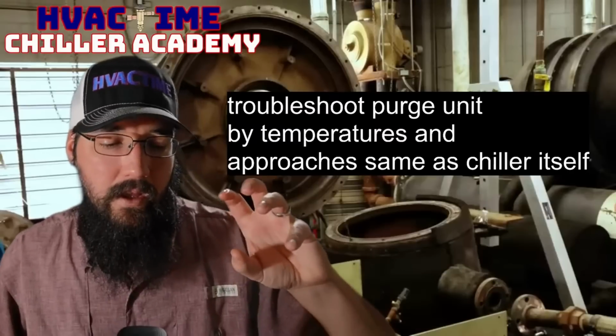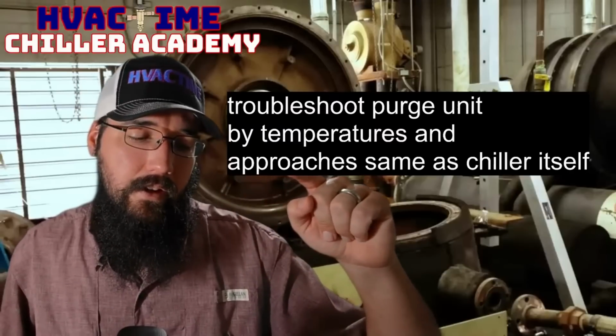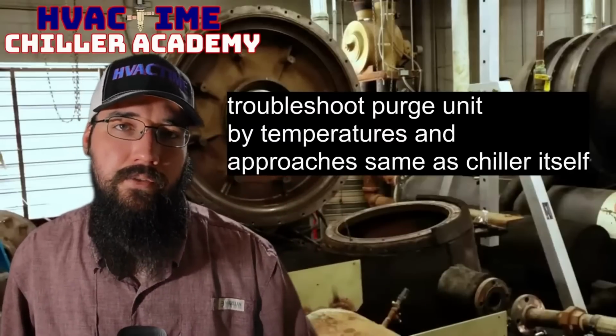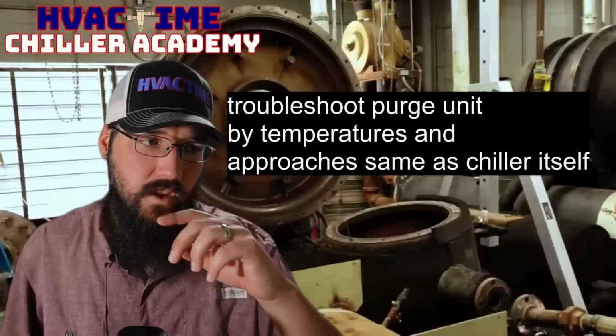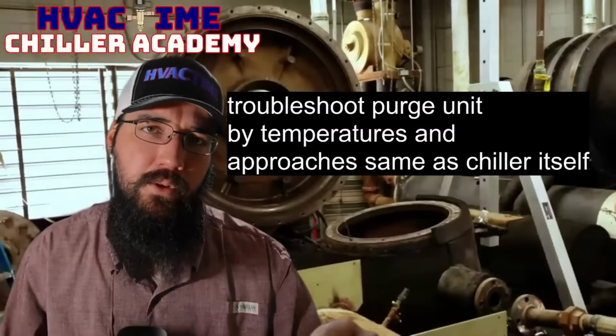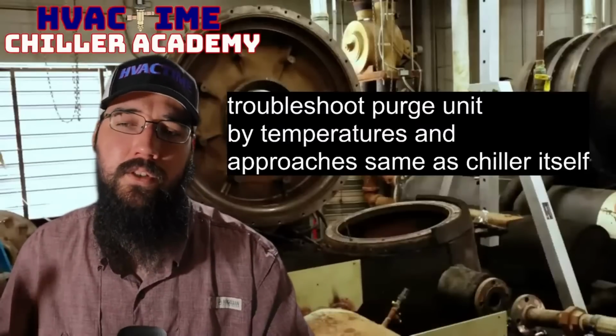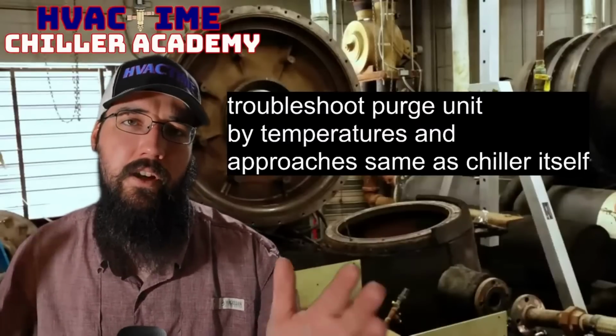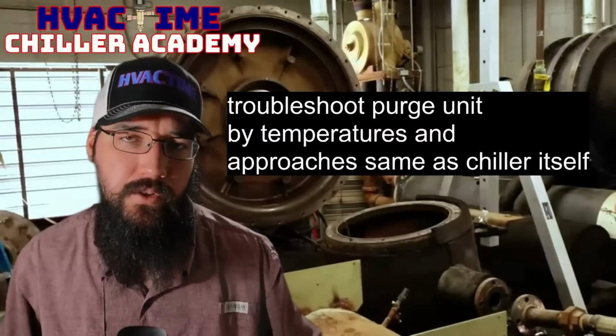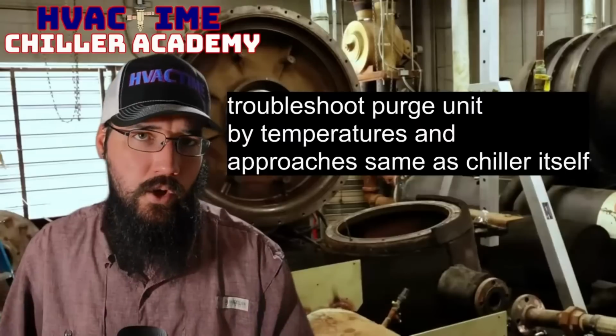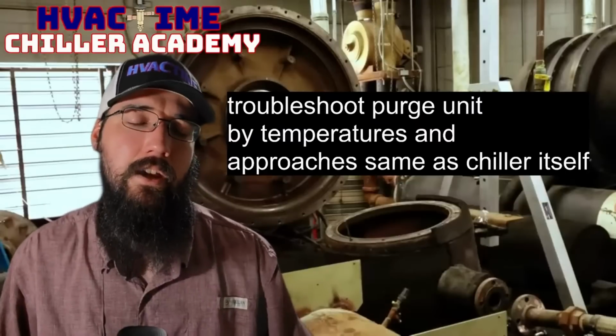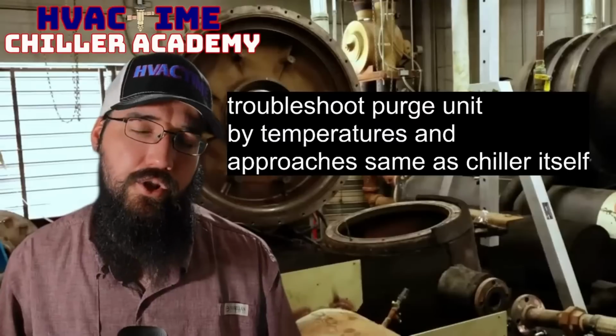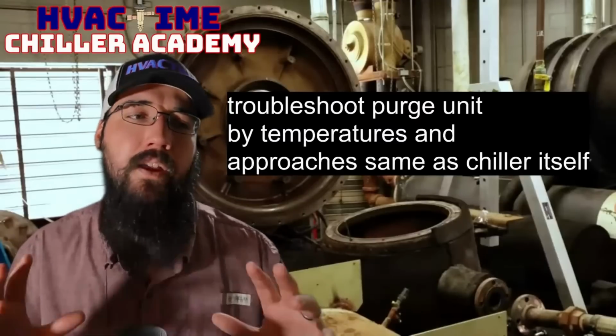And if the purge is still not functioning, where the evaporator is not pulling down, I know I've got non-condensables. I know I've got issues. I'm surging like crazy. I'm running high condenser approaches and pressures. So I know all that's happening, but the purge just ain't jiving. And I've got a fresh charge in there and it's still having trouble.